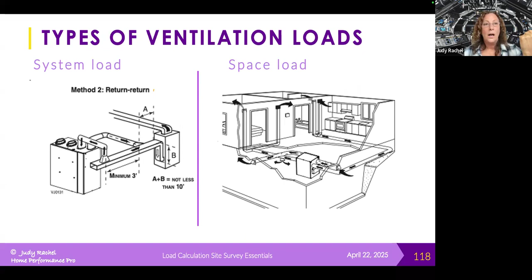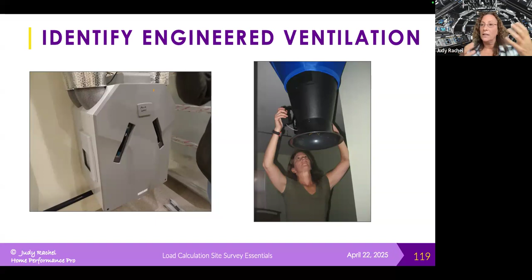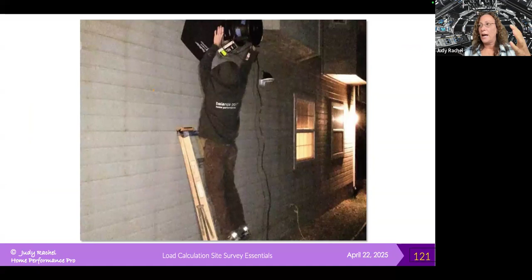ventilation load. So we need to identify what it is. Is it exhaust only? Is it supply only? Is it balanced? And does it have any heat recovery, and what is the percentage of heat recovery, or if it's an ERV, what is the percentage of latent recovery? And we need to measure that airflow so that we know how much air is being exchanged, whether it's at those recovery efficiencies or it's direct unconditioned air into the house, for our load calculation. Sometimes it's just challenging to actually measure the airflow in a ventilation system and figure out which grills are the ventilation system.